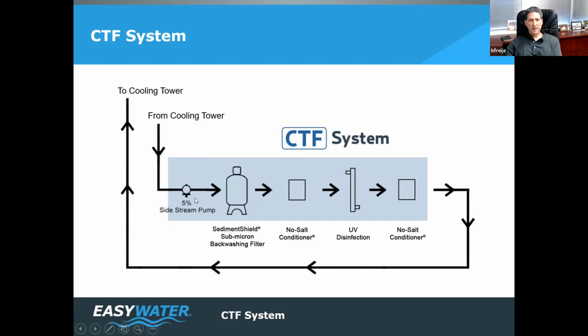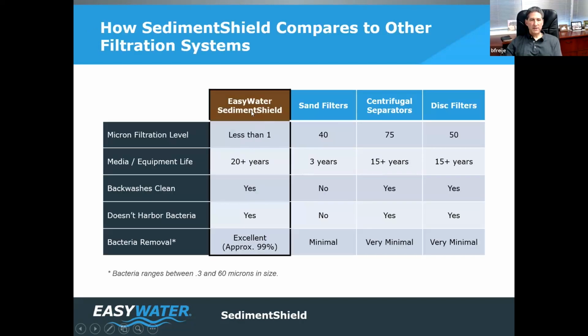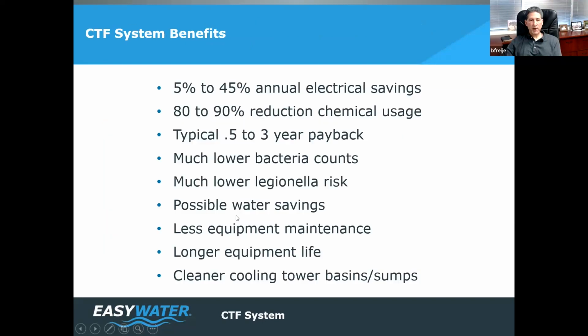It has its own pump. Pulls from the cooling tower system first goes through this sub-micron backwashing filtration system we developed called Sediment Shield. Then the no salt conditioner for scale and biofilm, which you already saw, then ultraviolet. Why this Sediment Shield? Well, for decades, we attempted to keep sumps cleaner using 40 micron sand filters or 75 micron sediment separators, but we failed miserably because all the particulate larger than 20 microns still settles even with sump sweepers. So we developed a less than 1 micron filtration system, and it's part of CTF.